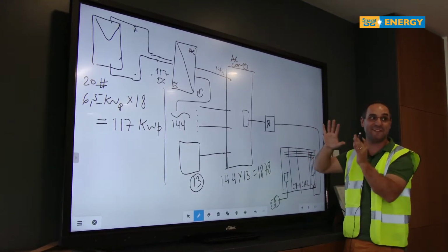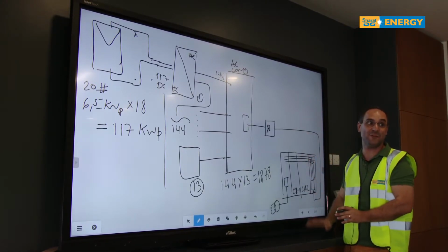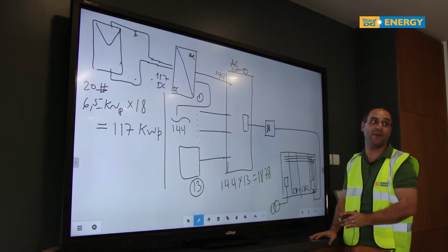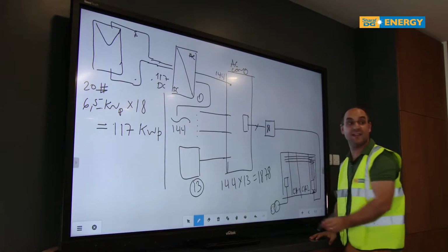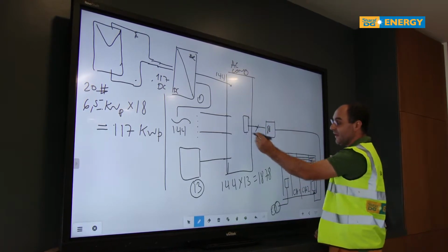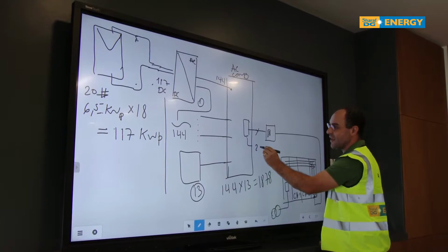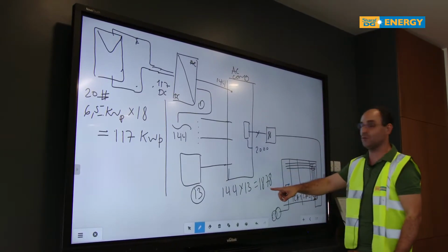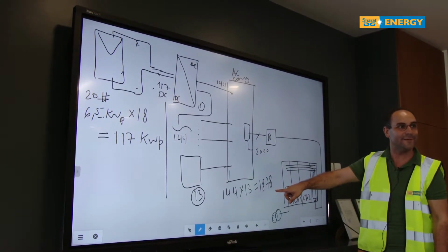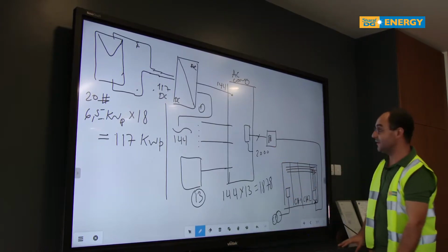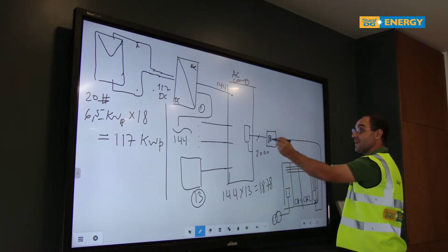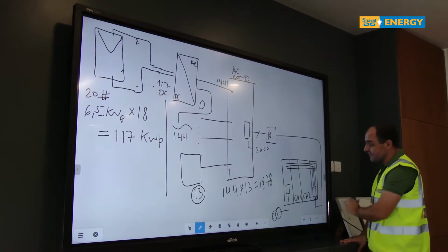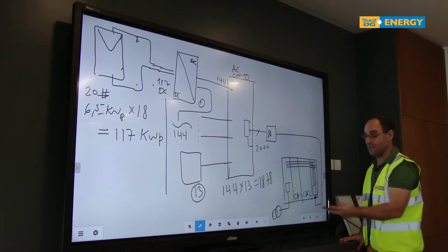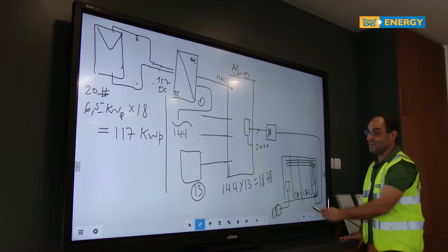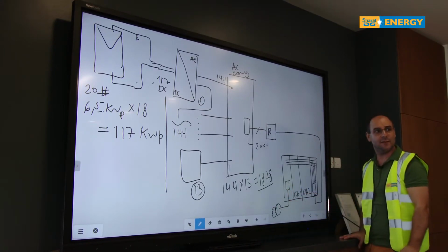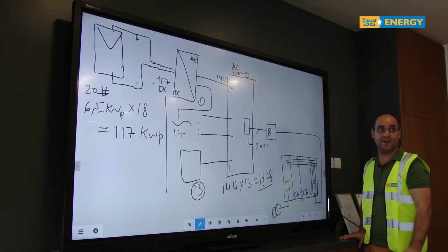Therefore the cables are designed accordingly. This breaker has to take at least 2,000 amps, because if you ask someone for a breaker of this rating, no one will give you anything - you have to go up. Then this isolator should be the same rating, and this breaker should be the same rating. This is a huge amount of energy.